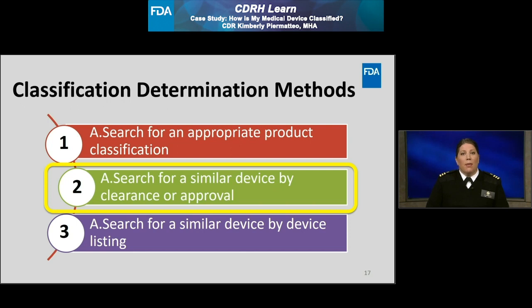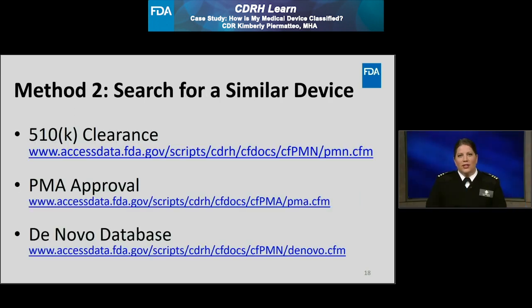Next, I'm going to discuss method 2, which is to search for a similar device by its clearance or approval. Using method 2, I will demonstrate that I will come to the same conclusion as method 1 by determining that the ITH product code is the most appropriate for a powered traction device. I can search for a similar device by 510K clearance or pre-market approval. For this method, it is important to note I would only be able to search for devices which have received 510K clearance or pre-market approval. Since most class 1 devices are exempt from 510K, I would not be able to find them by using this method.